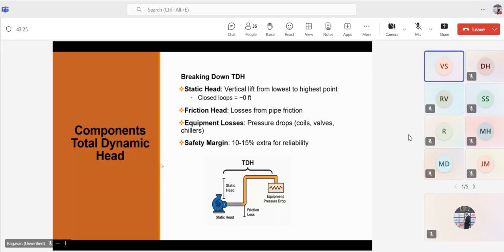Third one is the equipment pressure drop. Equipment pressure drop refers to the pressure drop that occurs as the water flows through the various components in the chilled water system, such as chiller, heat exchanger, cooling coil, and the control valves. Each piece of equipment impacts the flow to some extent, and the pump must provide enough head to overcome the losses. We will get this data from the manufacturer data sheet. They will provide the value of the pressure losses based on our flow rate.